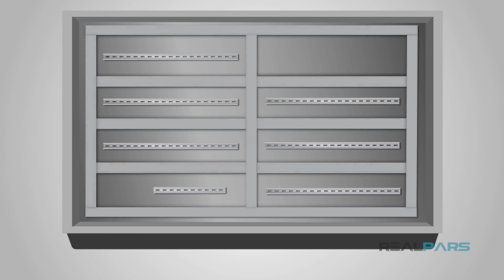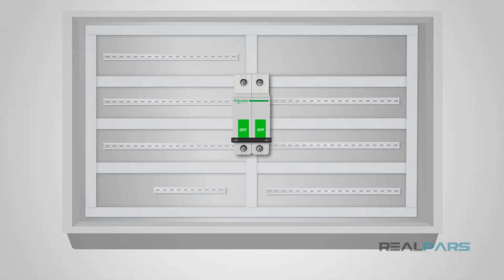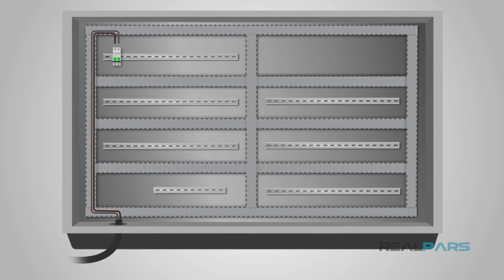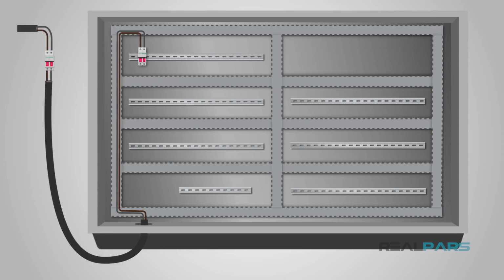Next, let's get into the electrical components of the control panel. The main circuit breaker is where the power comes into the control panel for all of the devices. This circuit breaker generally has a disconnect on the outside of the panel that allows us to shut off the power. Always remember the top side of the circuit breaker will still have power. The power that comes into the panel can be anywhere from 480 volts to as low as 120 volts.